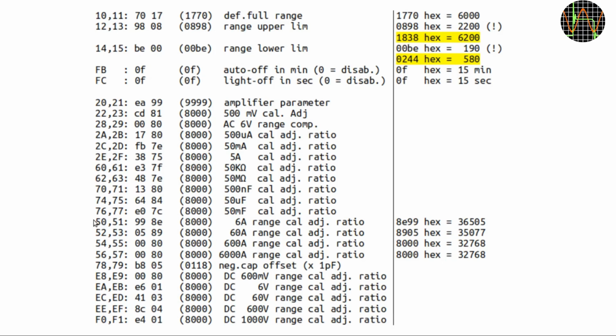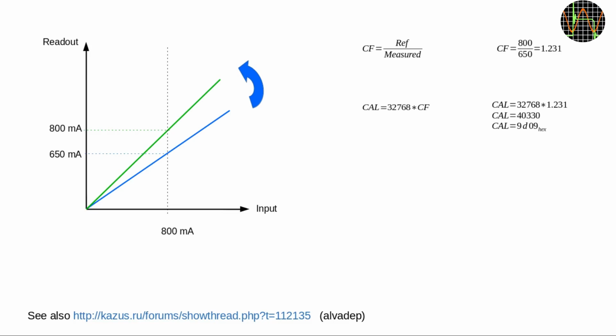The cal values for current start at address hex 50. Because this chipset is intended for 6000 count, the values are referred to as 6 amp, 60 amp and 600 amps, even though on the UT210E the ranges are 2 amp, 20 amp and 100 amps. The first surprise is that the 600 amp or 100 amp range was never calibrated from the factory, since it still has the default value of hex 8000 or 32,768 decimal. So how does the UT210 calibrate?